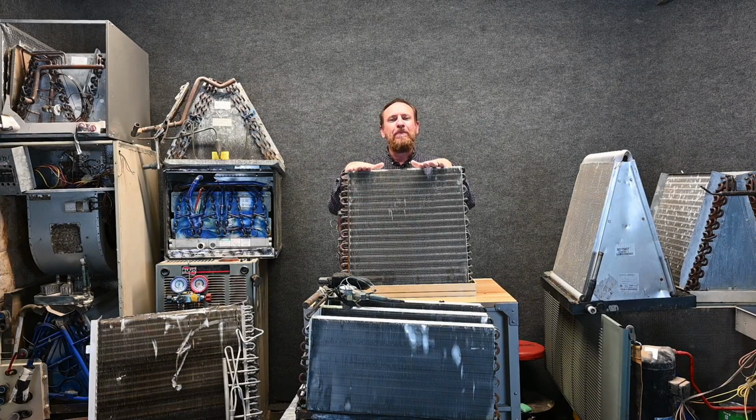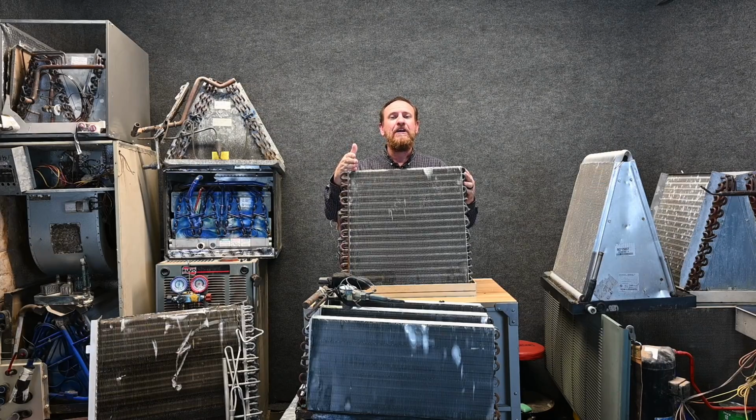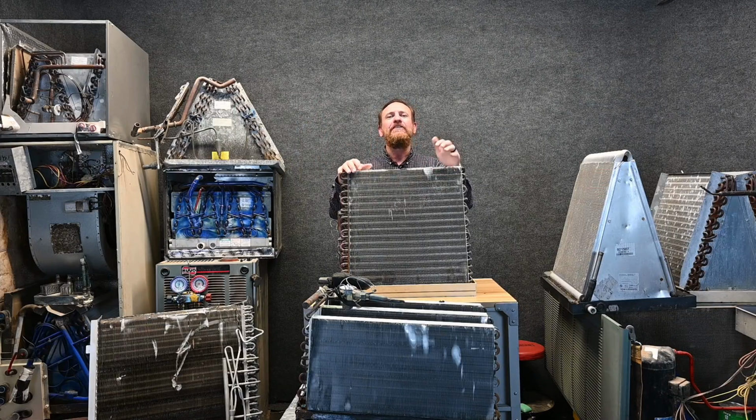Now, it's also very important that we size an air conditioner correctly, and we'll talk about this later as well. But if we put in an air conditioner that's too large, it will not dehumidify. And if we do not dehumidify, we're cooling the house down sensibly very fast, but the moisture level will be much higher, and the customers will be very uncomfortable. Like, it's 65 degrees, I should be freezing, but it feels hot and clammy.